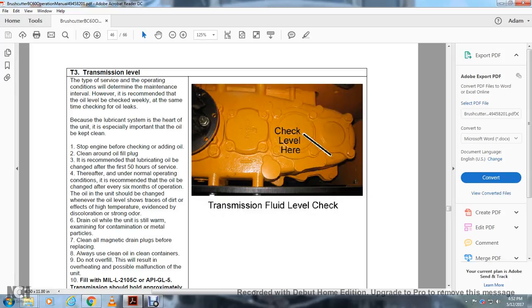It is recommended that the lubricating oil be changed after the first 50 hours of service. Thereafter, under normal operating conditions, the oil may be changed every 6 months. Under severe operation, the oil should be changed whenever it shows traces of dirt, effects of high temperature, discoloration, or strong odor. 6, drain oil while the unit is still warm, to carry off contaminating particles.